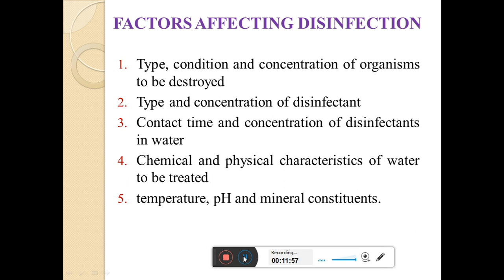Then, the physical and chemical characteristics of the water to be treated will also affect the disinfection process. The nature of suspended solids is an important factor and must be evaluated carefully. Substances like ammonia, iron, manganese, and organic matter interfere with the disinfection process. The organic matter will react with most oxidizing disinfectants and that will reduce the effectiveness of the disinfection. Turbidity also reduces the effectiveness of disinfectant by absorbing and by protecting the bacteria. That's why physical and chemical characteristics also affect the efficiency of disinfection.